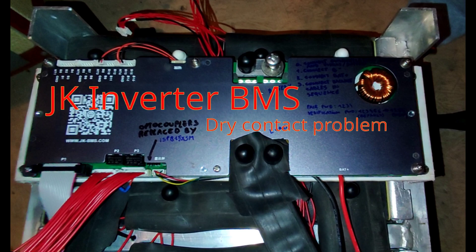In this video I will discuss the JK Inverter BMS dry contact problem. The issue being that sometimes on some boards one or both relays mysteriously will not toggle even though the conditions to switch them have been reached.